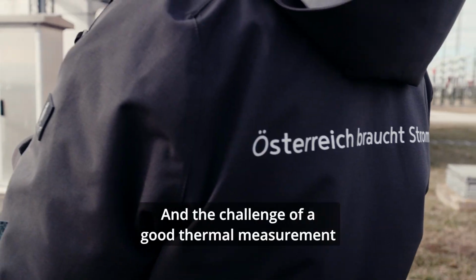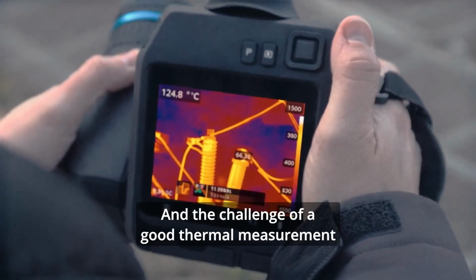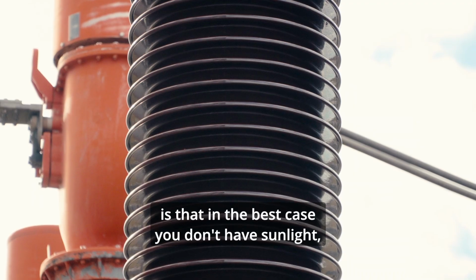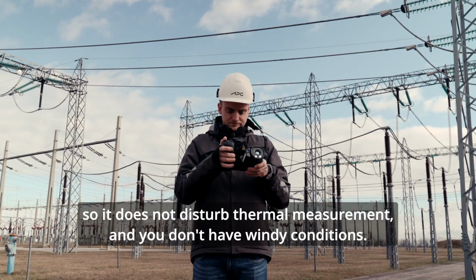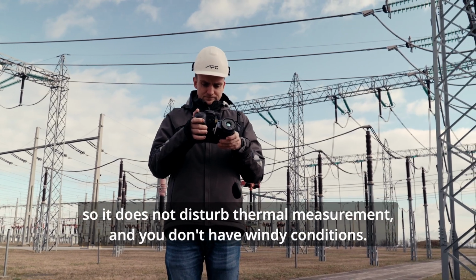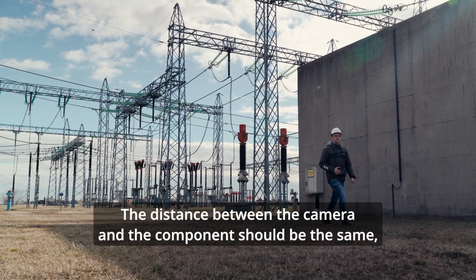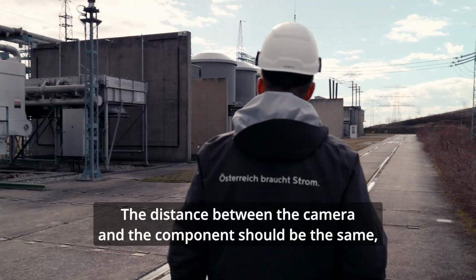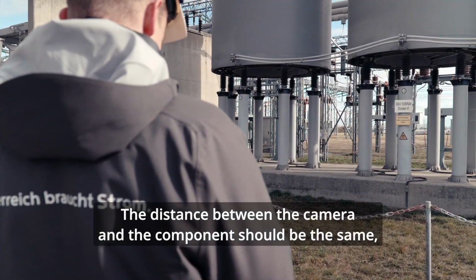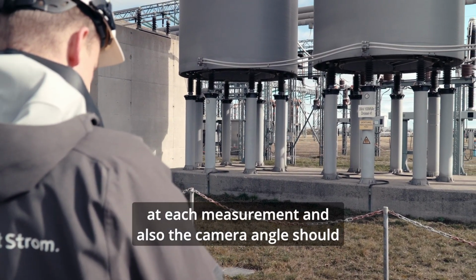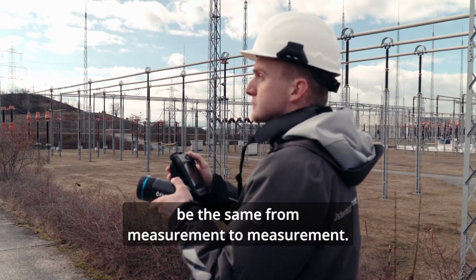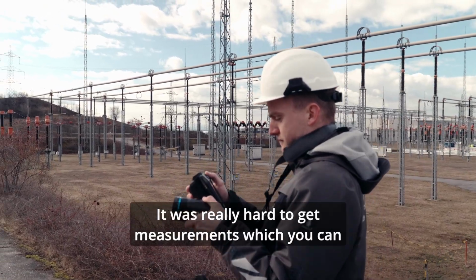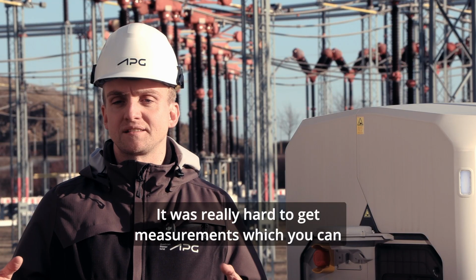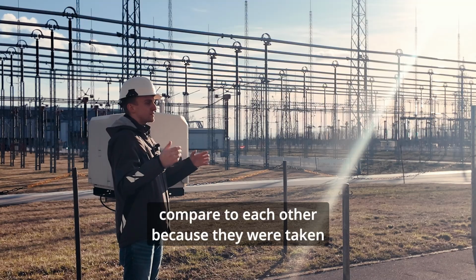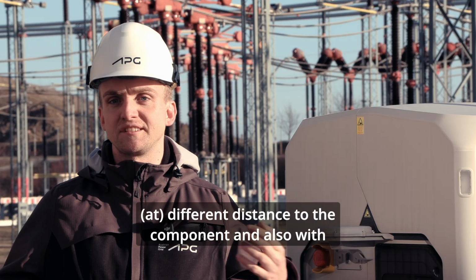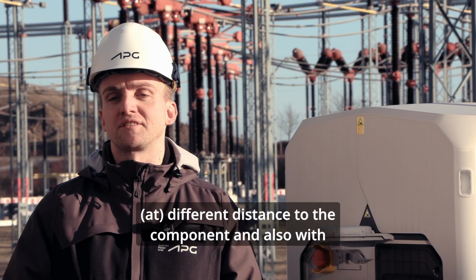And the challenge of a good thermal measurement is that in the best way you don't have sunlight, since it disturbs thermal measurement, and you don't have windy conditions. The distance between the camera and the component should be the same at each measurement, and also the camera angle should be the same from measurement to measurement. It was really hard to get measurements which you can compare to each other because they were taken at different distances to the component and also with different camera angles.